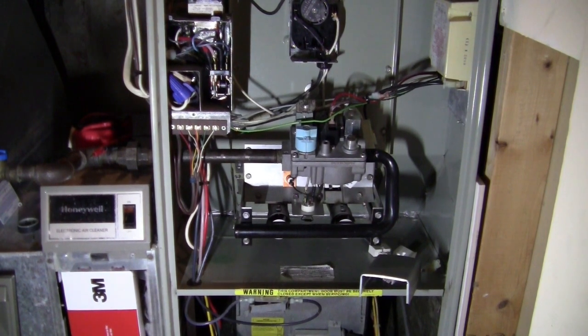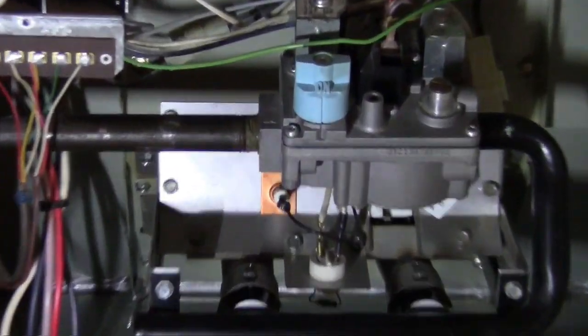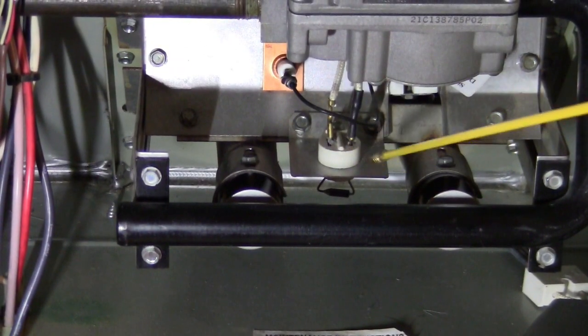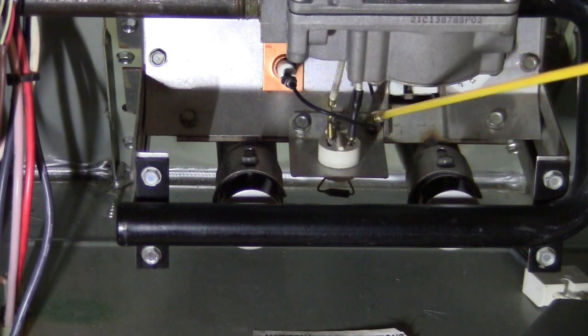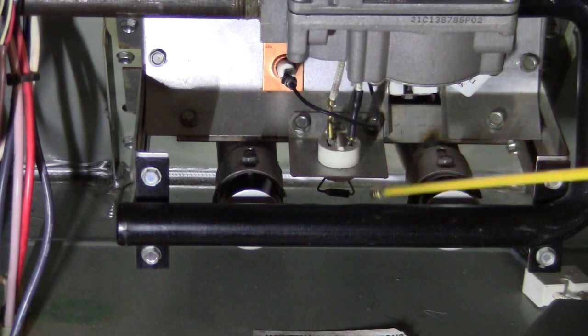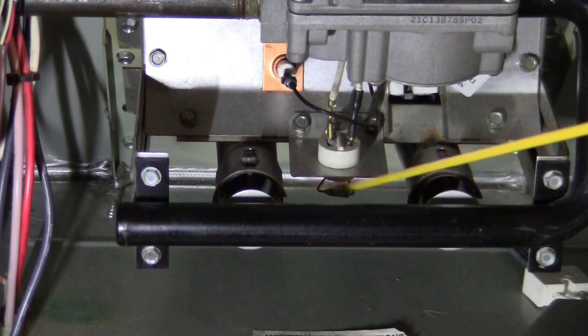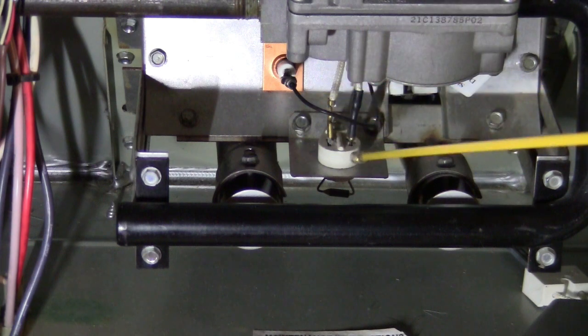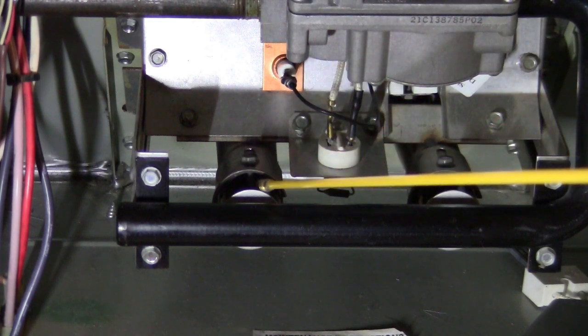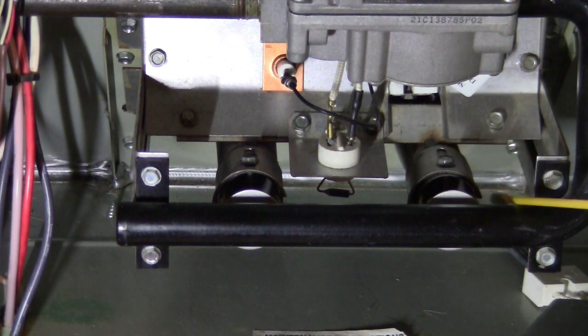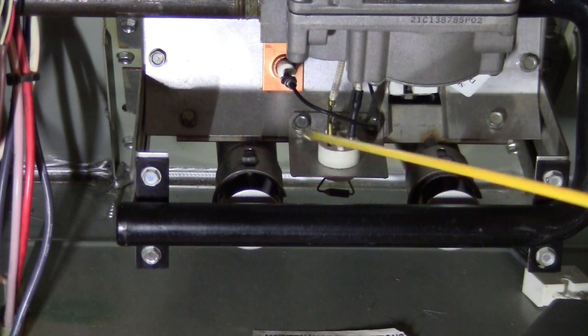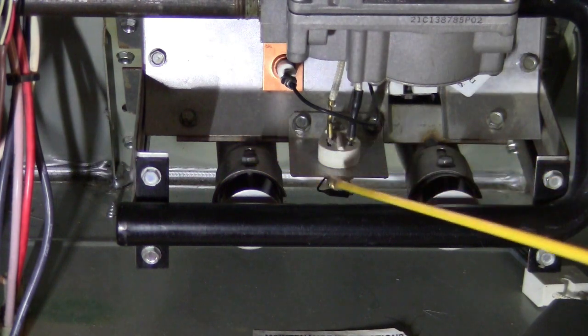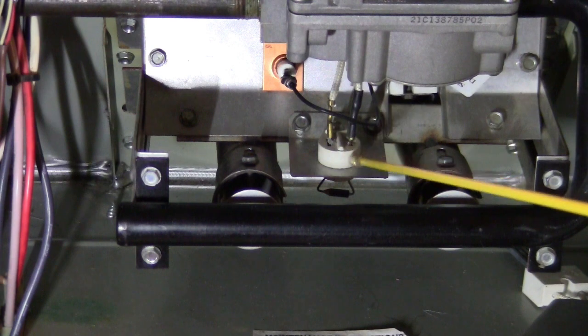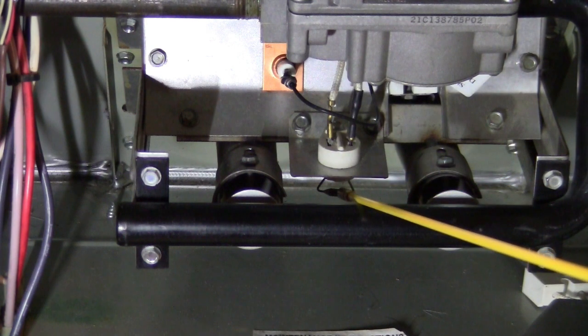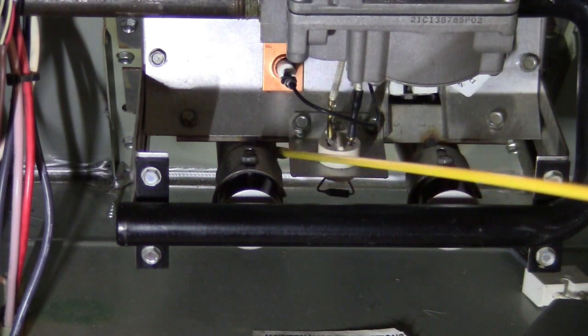There is another controller over here we need to introduce. See that thing? It used to have two connections to connect to the sensor. There's one small stop down here, maybe a sensor. What is this thing doing? This is called the gas overflow detector. The gas is supposed to be sucked up into that and burn inside there, and nothing should come out from here. If the fire is burning over here, then you have a big problem. So this sensor is here to detect if any gas or fire overflows to the outside.